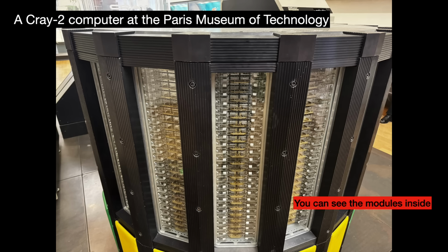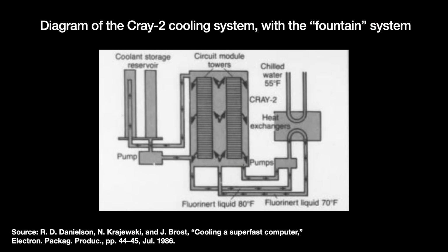During operation, Fluorinert liquid is pumped into and up the vertical module towers at a rate of about 70 gallons per minute, and then flows between the module stacks like a waterfall, making direct contact with the chips. After this, the liquid, now about 5 to 6 degrees Celsius warmer, goes to a heat exchanger where its heat can be offloaded to a normal water loop.